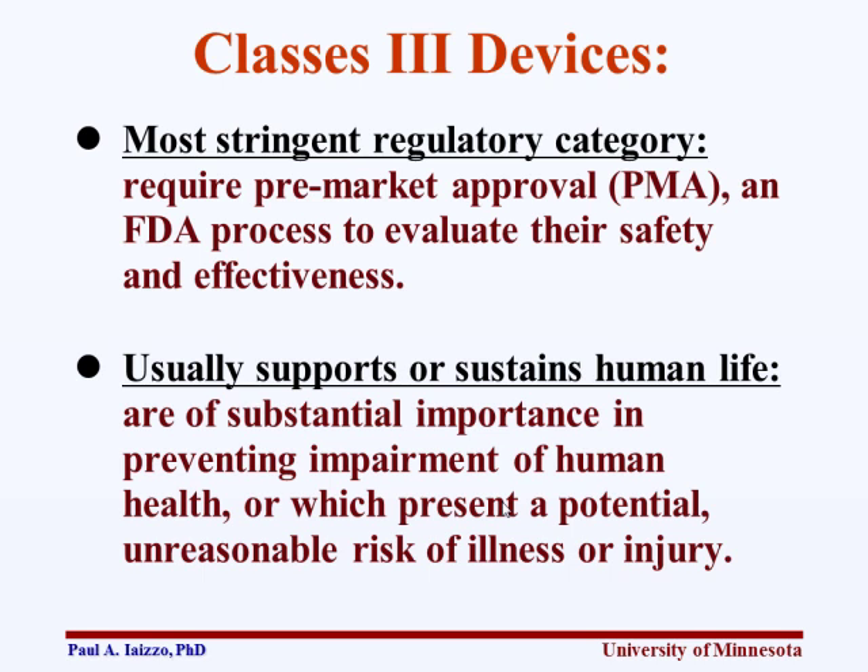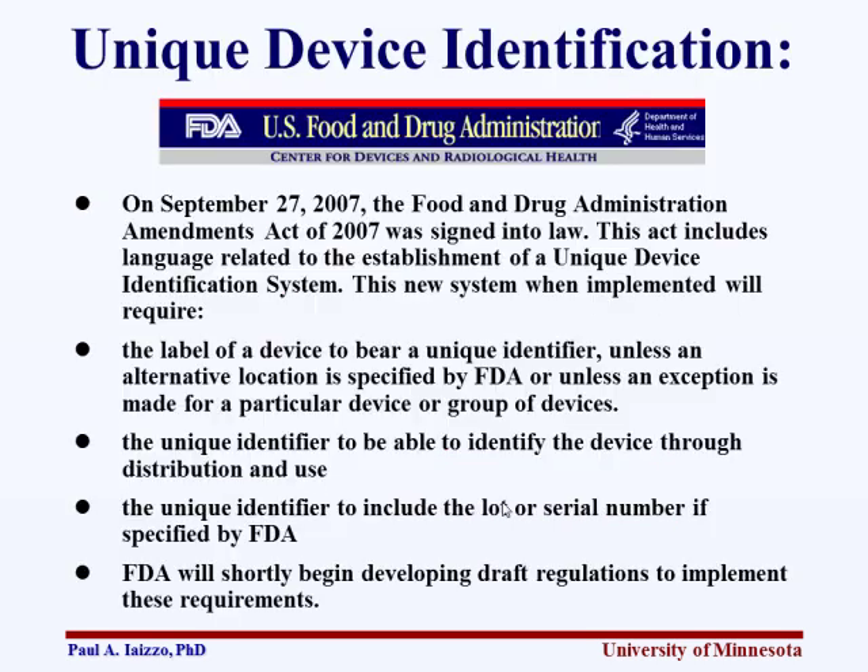Class 3 devices generally support or sustain human life, with substantial importance for preventing impairment of human health, or presenting a potential, unreasonable risk of illness or injury. Unique identification is required by the FDA. All of this information is on their website — they have a great website where you can write in a question and get an electronic response. It's really important to build relationships with your regulatory boards, whether CE mark, FDA, or others — get to know them, build a relationship, and network with them.